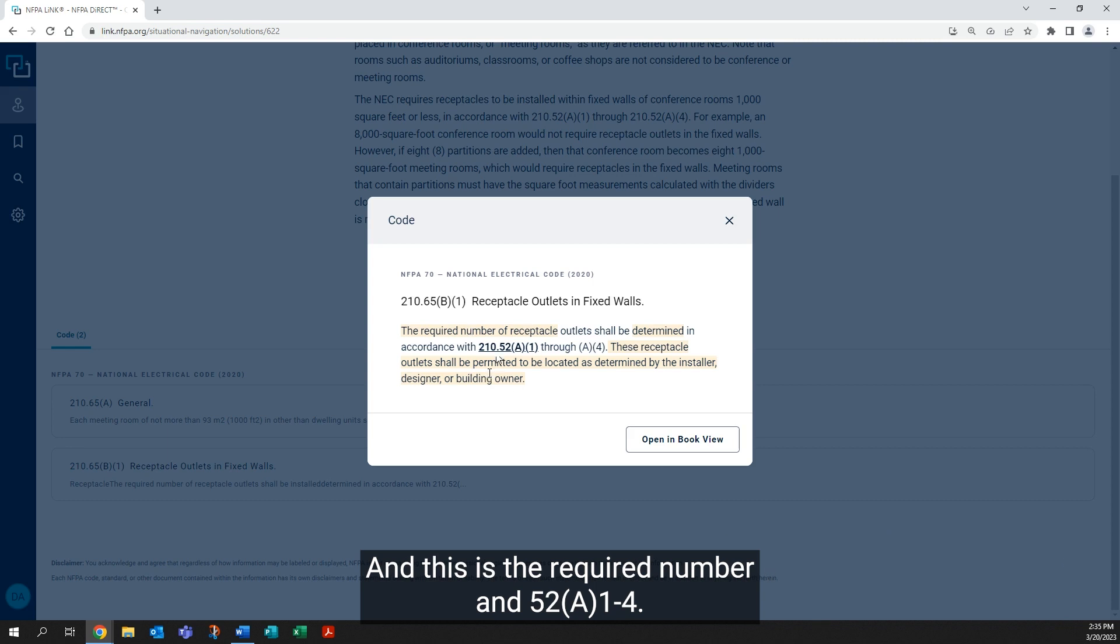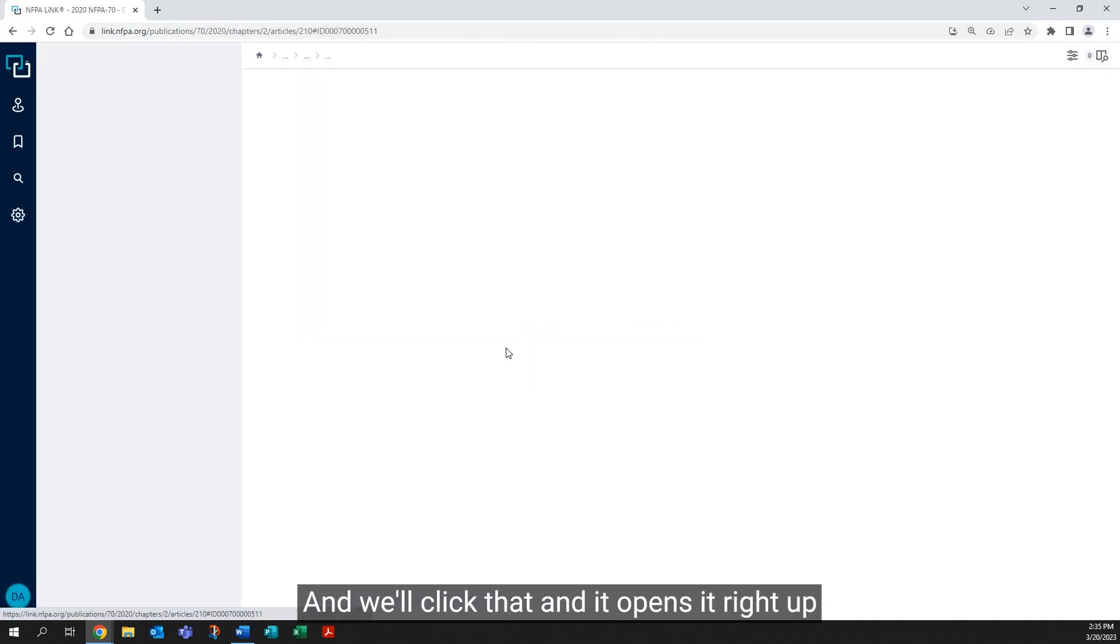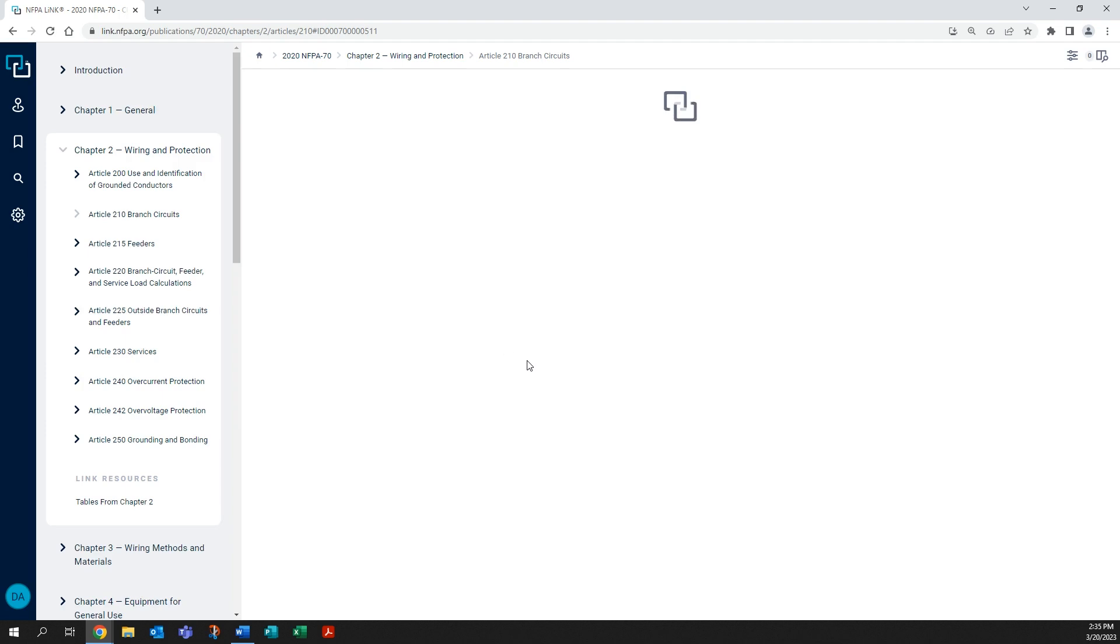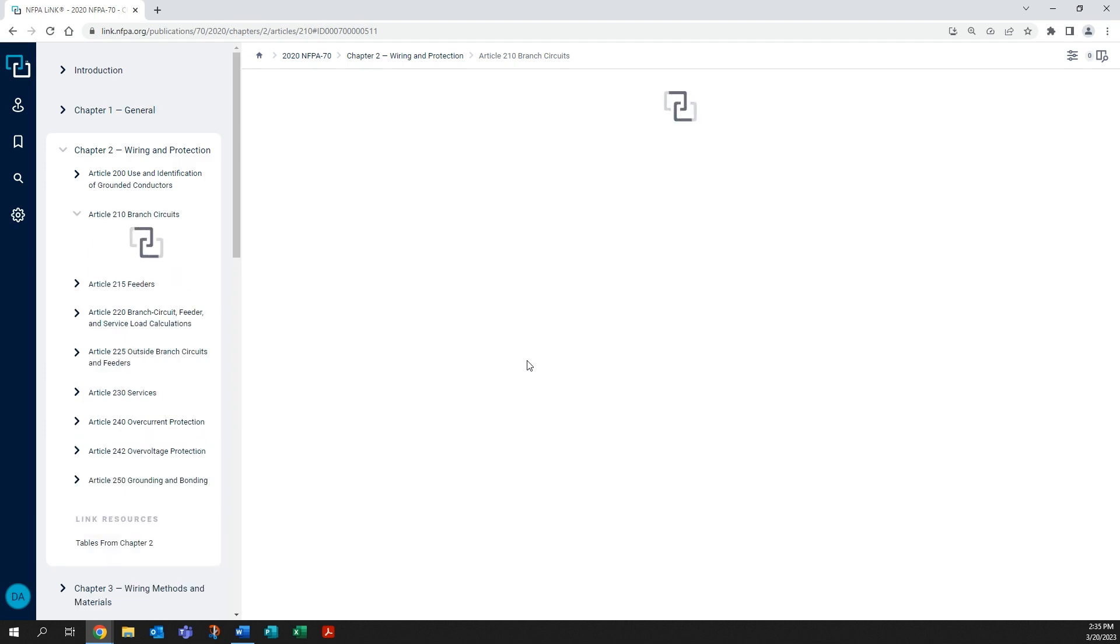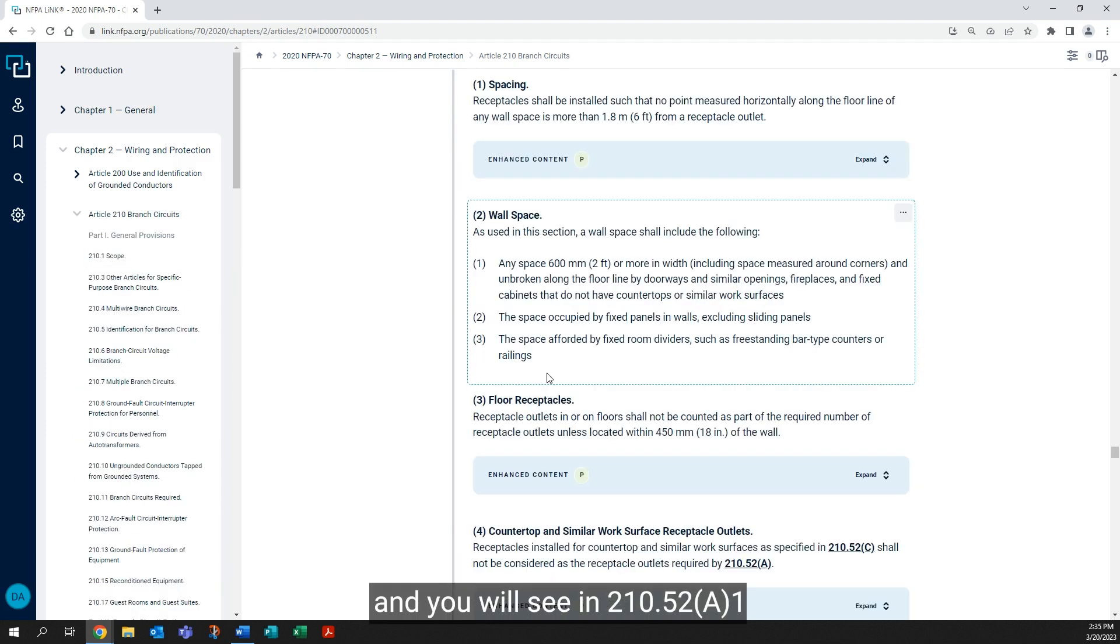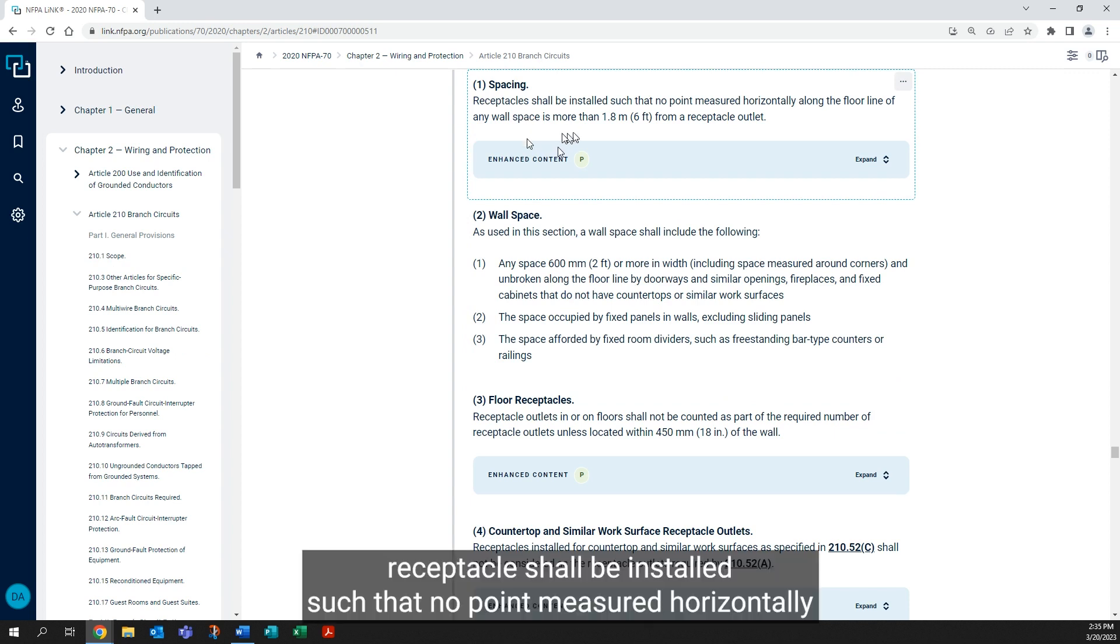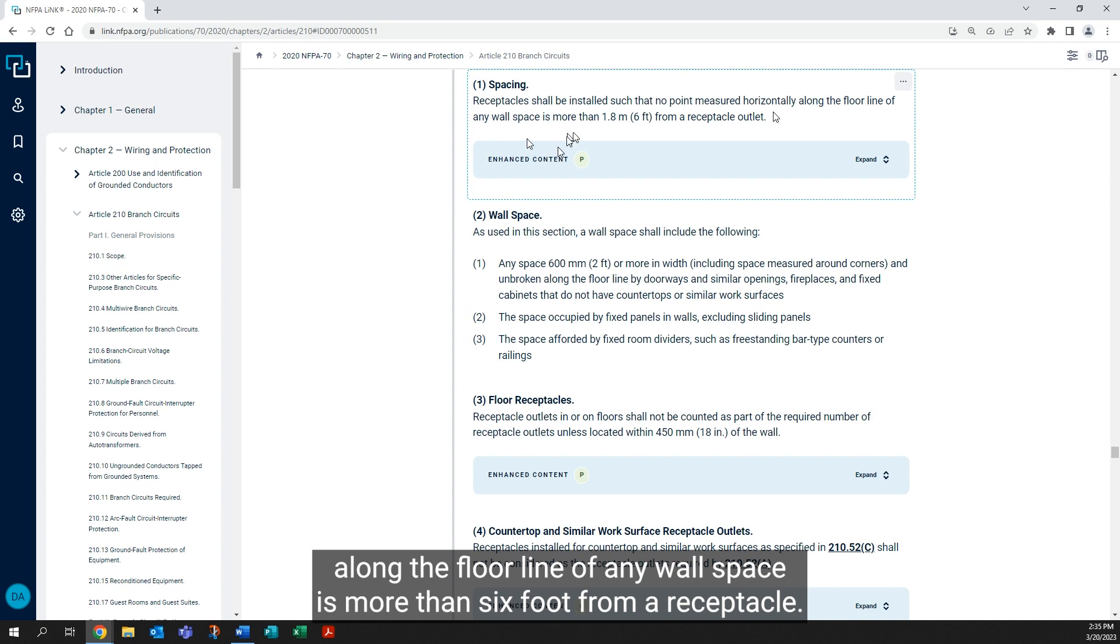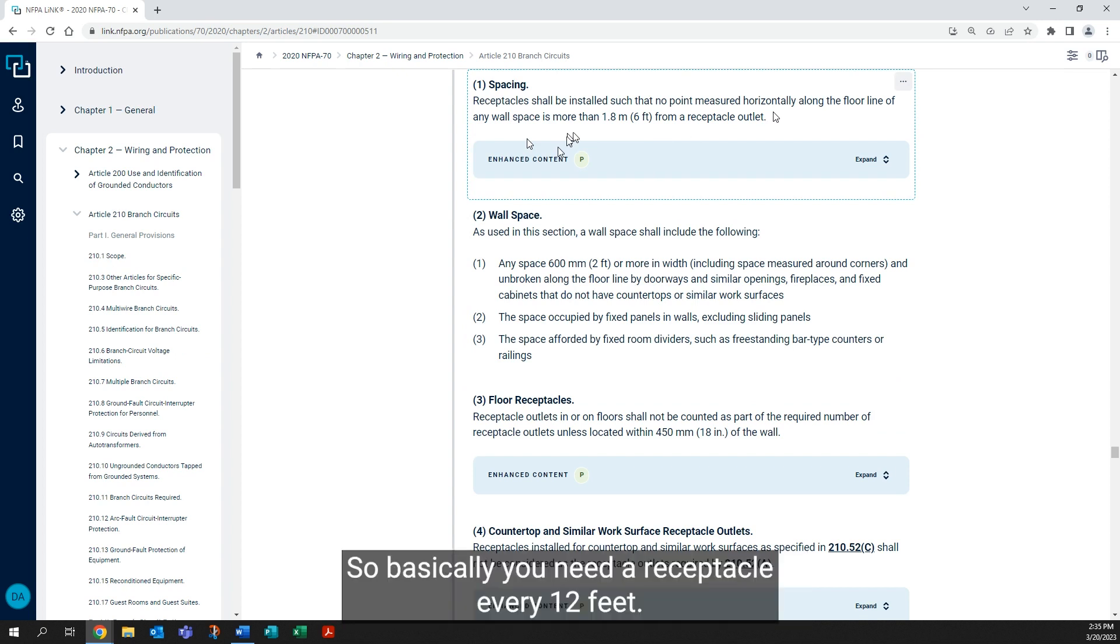You will see in 210.52 a1: receptacles shall be installed such that no point measured horizontally along the floor line of any wall space is more than six feet from a receptacle. So basically, you need a receptacle every 12 feet.